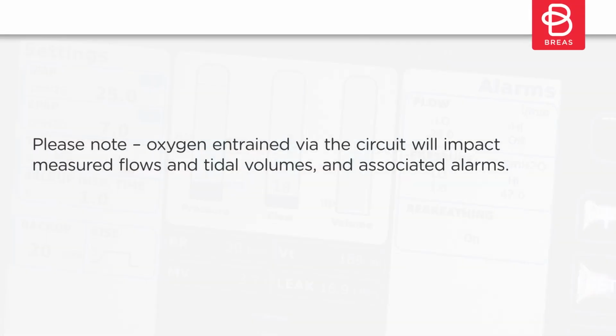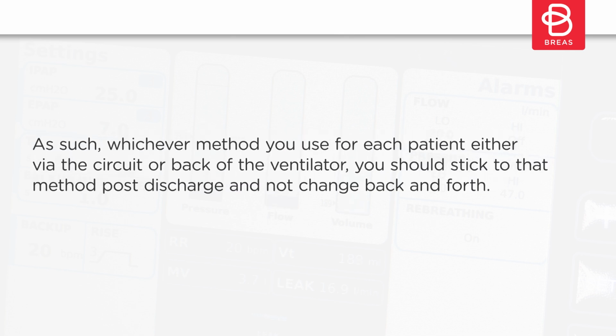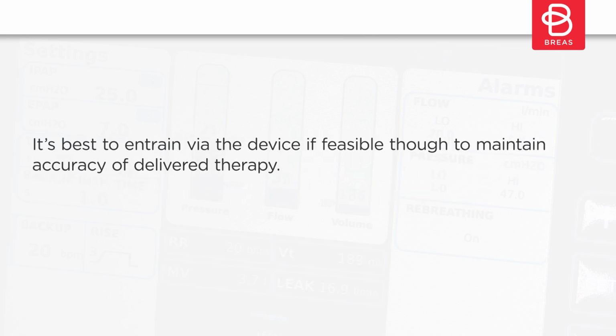Please note, oxygen entrained via the circuit will impact measured flows and tidal volumes and associated alarms. As such, whichever method you use for each patient, either via the circuit or back of the ventilator, you should stick to that method post-discharge and not change back and forth. It's best to entrain via the device if feasible though, to maintain accuracy of delivered therapy.